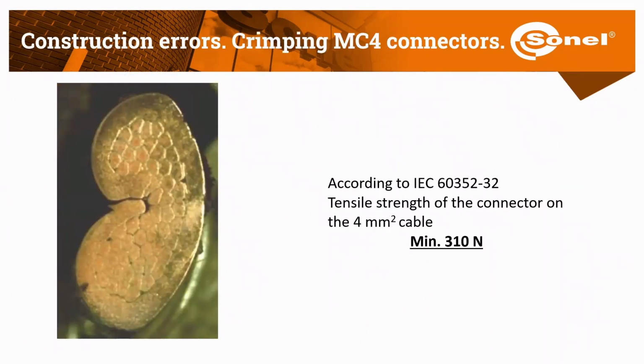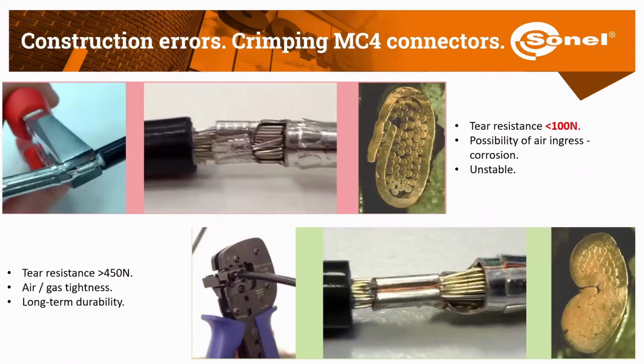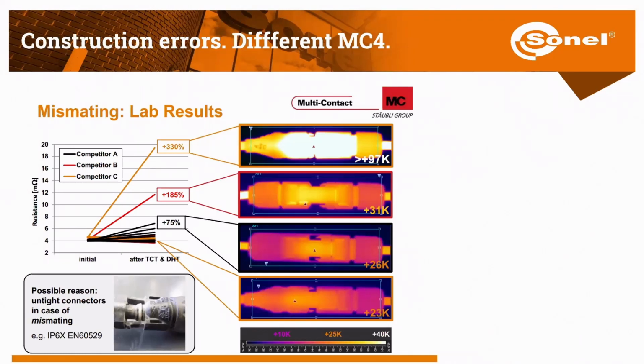According to the standard, the strength of the connector of a 4 millimeter cable is 310 newtons, but frankly speaking, this is almost impossible to achieve. As we can see in the picture, the strength of the cable is around 100 newtons. Also, improper connectors might cause problems in the future, such as overheating or even a short circuit of the whole installation.